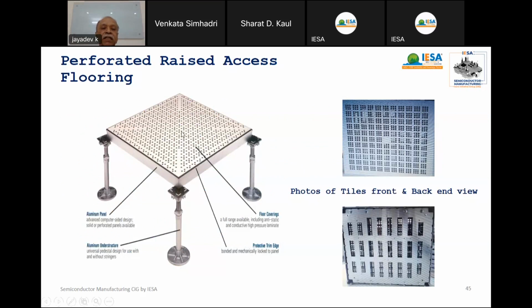So this is how a perforated grate tile looks. It's 600 by 600. This is 44 mm die-cast aluminum. It uses pedestals. If you see this actual picture, taken from the side, from the top, it looks like this. From the back side it looks like this. In the back side we have accessories. You can control the volume. You can increase or decrease the quantity of air flowing through the tiles. So they are die-cast materials, 44 mm thick, with an ESD surface.